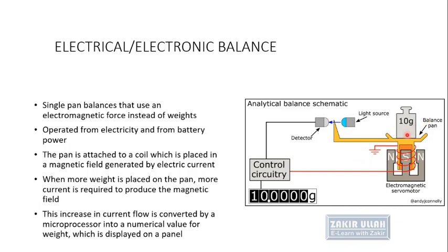This is the schematic diagram of the electrical balance. The weight is placed on the pan and below there is an electromagnetic field. When more weight is placed, more electromagnetic field is created. This strikes a detector area which is connected with the circuit. When any weight is placed on the pan, the electromagnetic field is created and converted into units and a numerical value, which is displayed on the balance's display.